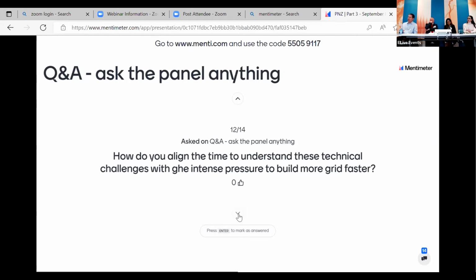Where batteries can really help, and they do help, is they can provide super fast frequency response. Without that, we wouldn't be able to operate the system at these low inertias. Currently, the lowest system inertia ever goes down to is 140 GVA seconds. That number won't mean much to you, but what it means is if the market ever gives less inertia on the system than that, we bring on extra inertia to bring it back up.